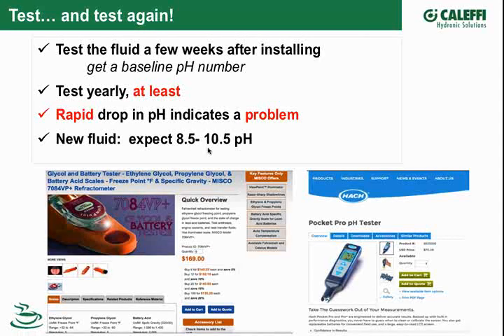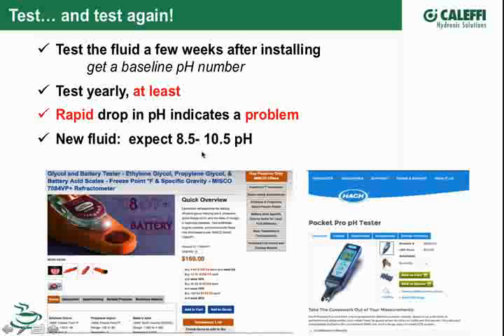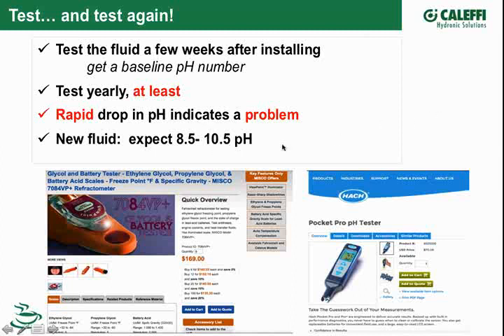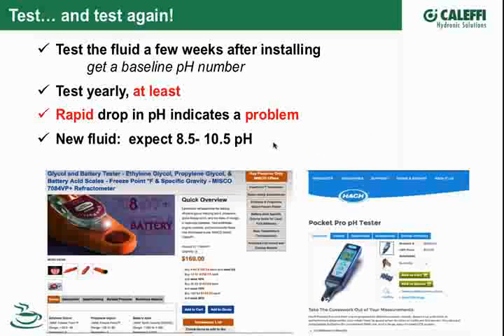Does pH ever go up, or does it always go down as glycol ages? It can go up, and that's usually a telltale sign you've got a corrosion problem. If you're using aluminum and the pH goes up over 10.5, you guaranteed have a problem with your aluminum heat exchanger - the aluminum is breaking down and affecting the fluid pH. It's forming aluminum hydroxide, and that hydroxide pushes up the pH.